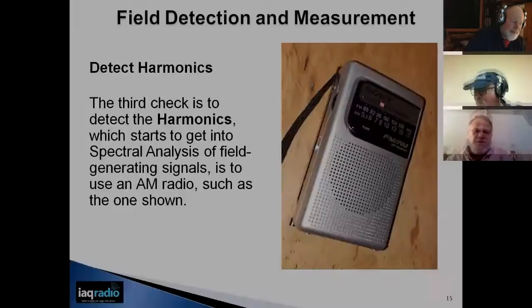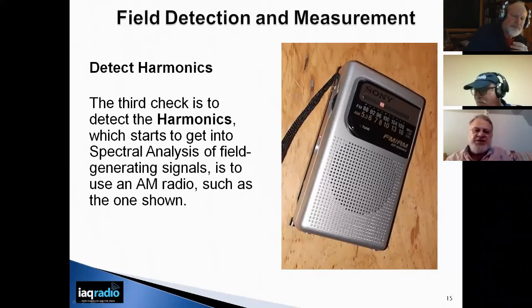The AM radio portion is an inexpensive check for detecting harmonics, because if you can detect them, it tells you they are intense near the low end and high enough in frequency to encroach onto the AM band. I've had harmonic sources encroach onto FM, and some have even encroached right into the radio frequency, into the 800 megahertz band, and caused interference. So the AM radio is a very inexpensive way to check.